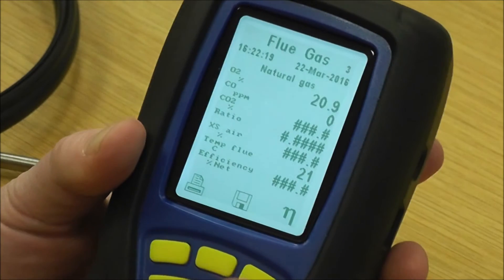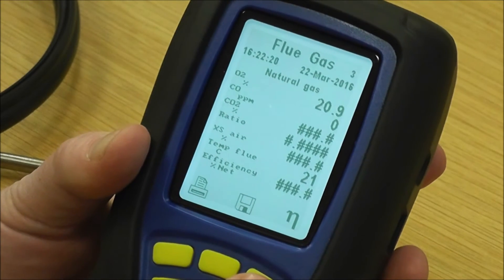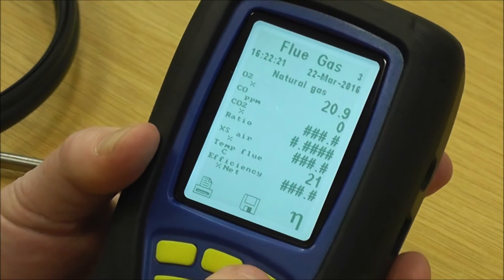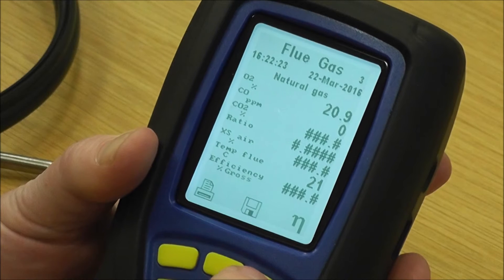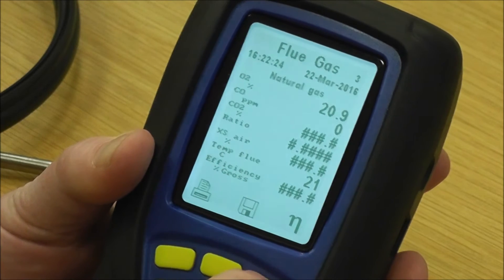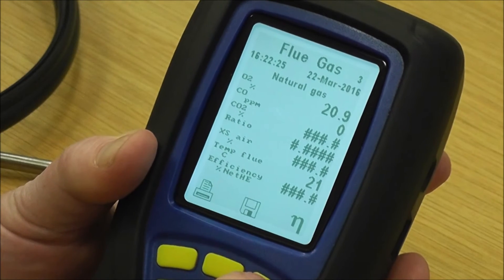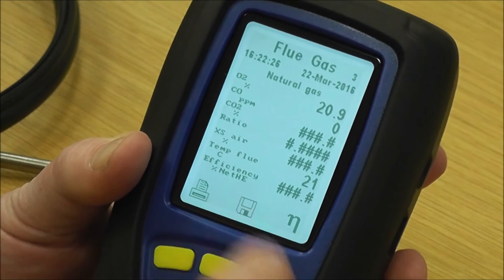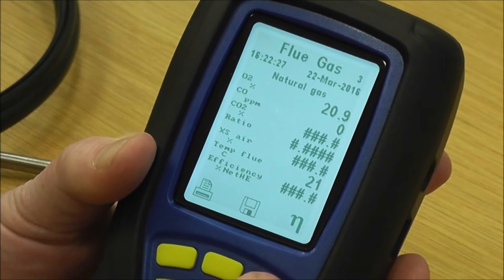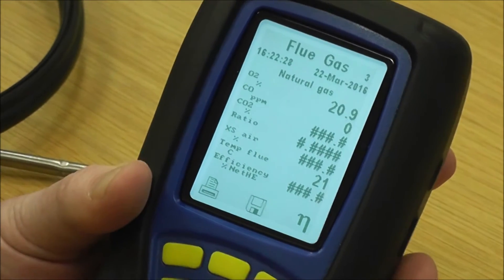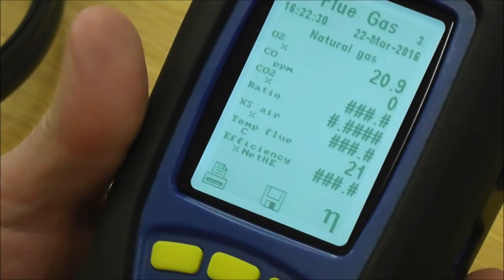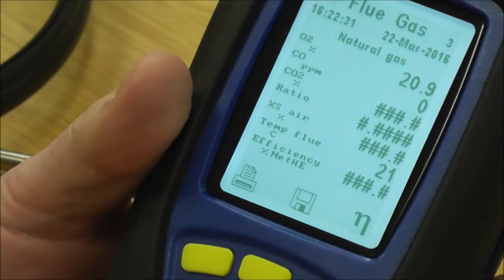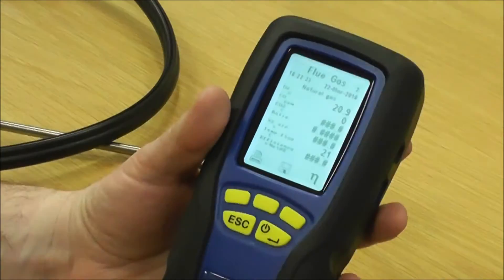This key here is for changing the efficiency. You've got efficiency net, efficiency gross, and efficiency net HE for your high-efficiency or condensing boilers.